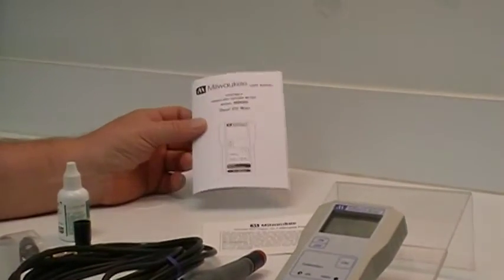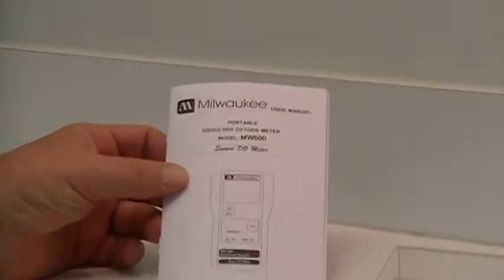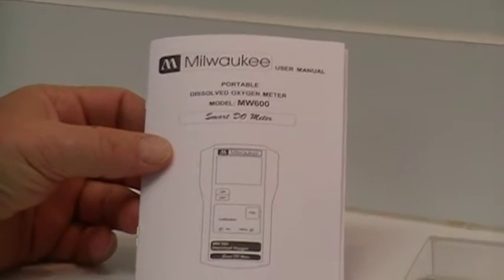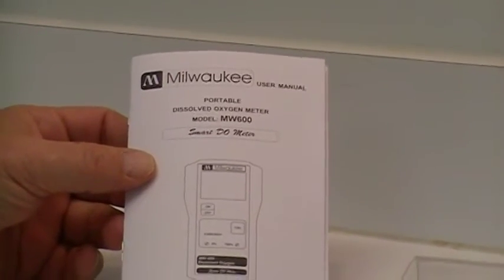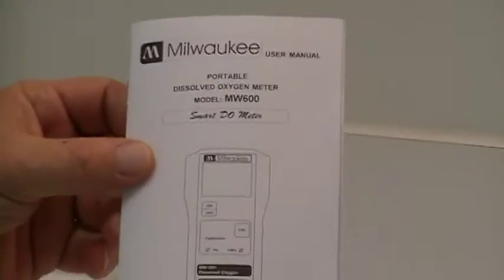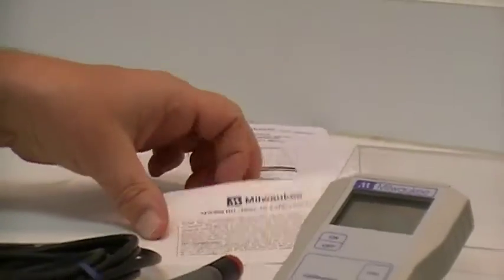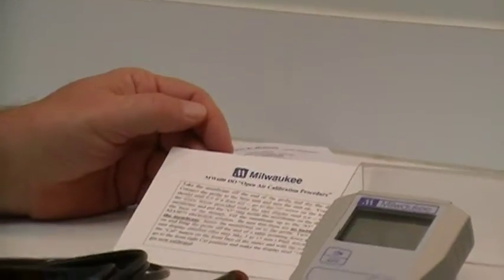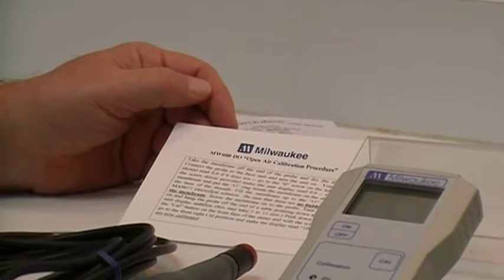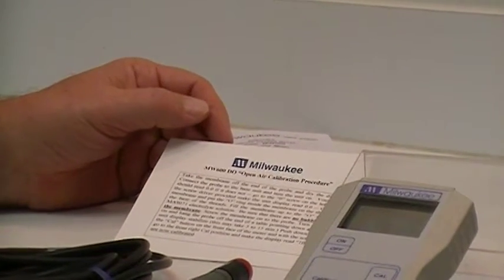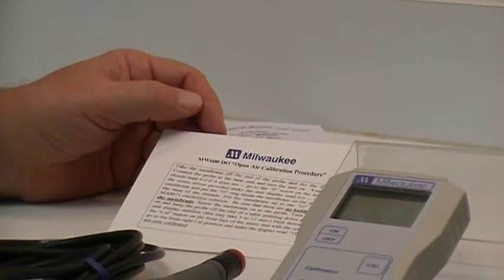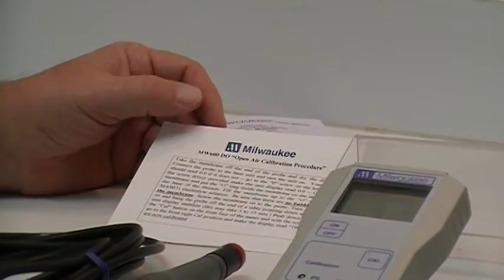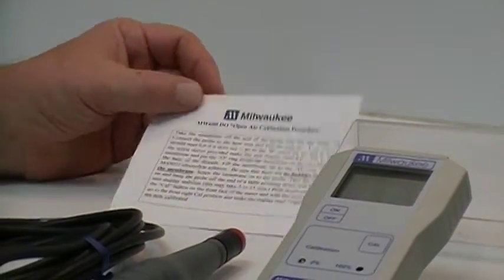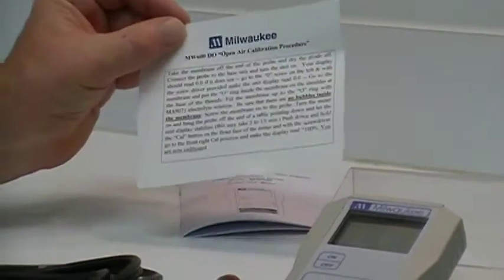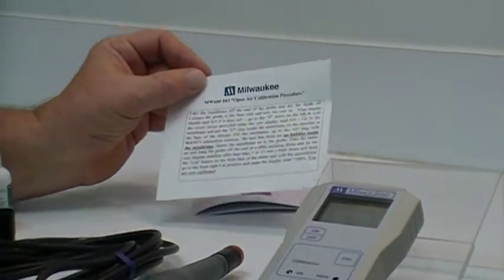Today we're going to do a calibration procedure for the dissolved oxygen meter model number MW600. When you first open up your unit, you're going to find an operator's manual. Also included with your unit is the MW600 dissolved oxygen open air calibration procedure card. This is the open air calibration procedure that we would like for you to proceed with rather than what's in the manual. This is much easier, and it's just as precise.